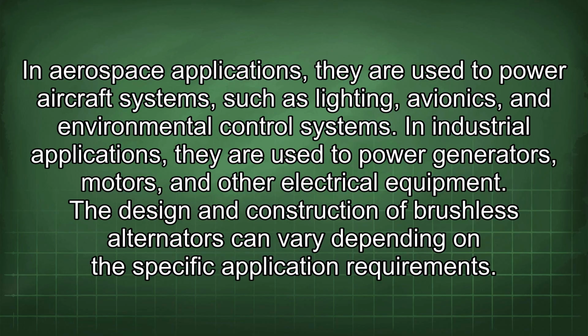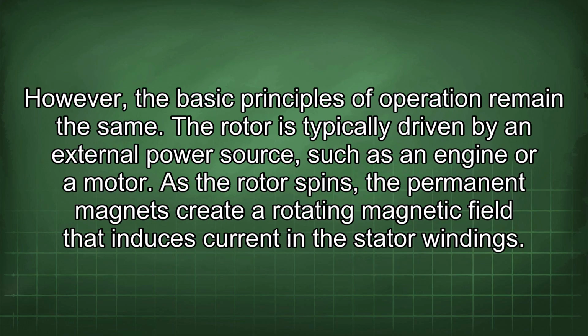The design and construction of brushless alternators can vary depending on the specific application requirements. However, the basic principles of operation remain the same. The rotor is typically driven by an external power source such as an engine or a motor. As the rotor spins, the permanent magnets create a rotating magnetic field that induces current in the stator windings.